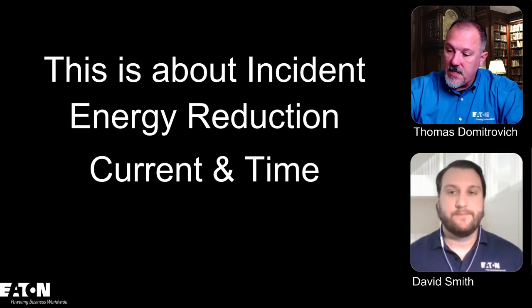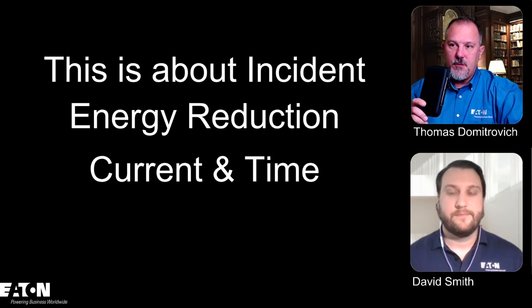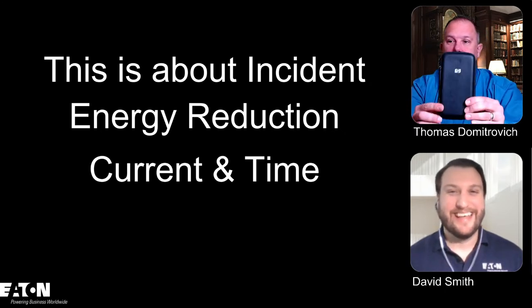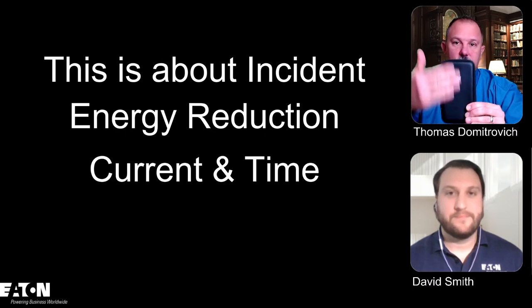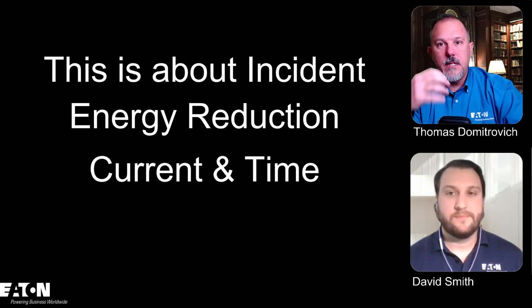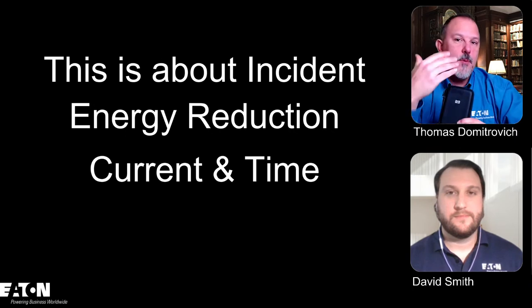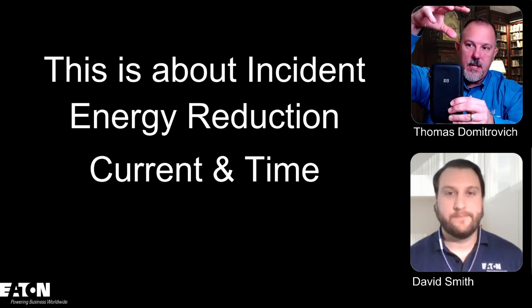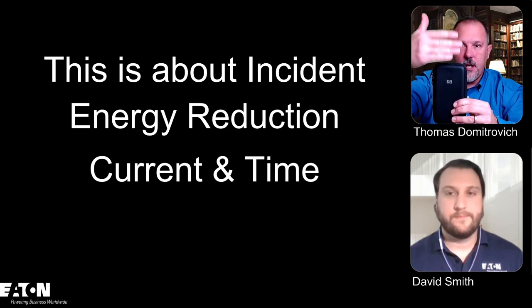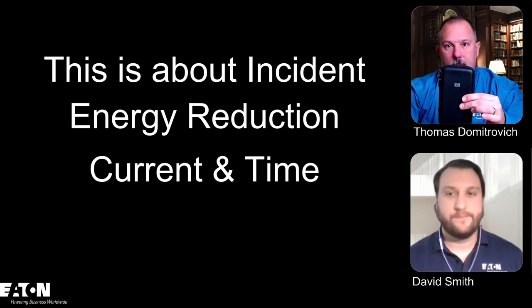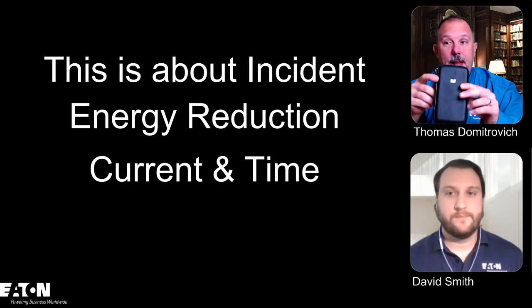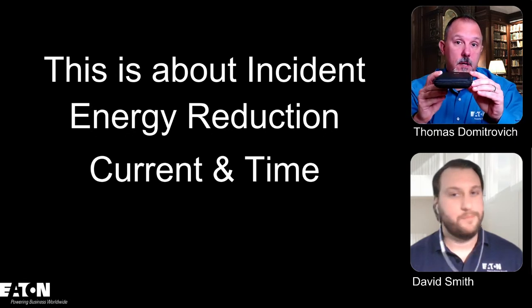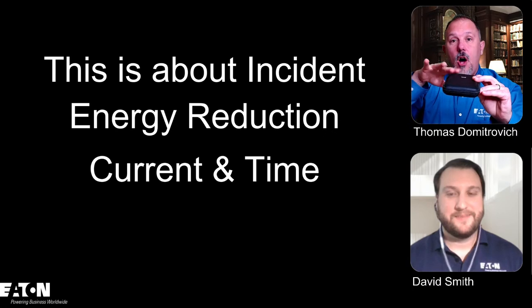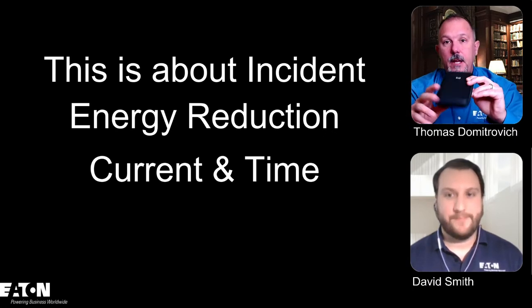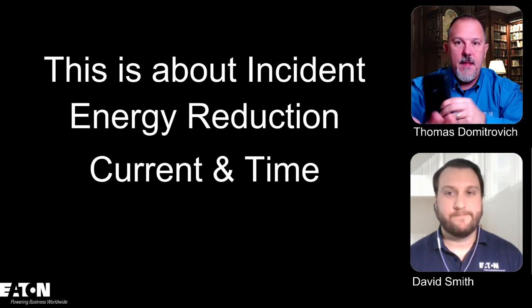So when you're working on a piece of equipment, and I'm going to use my HP calculator box for this, if this is my bus and it's up and down, that's a vertical bus. We know that the arc travels opposite of the source. So if my source is here on top and I have a fault here, the current is going to flow down and out the bottom. If I'm working on equipment and my bus is this way, that's bad, because now all of that energy is coming straight at me. I'm not having the benefit of the energy coming down and then out.